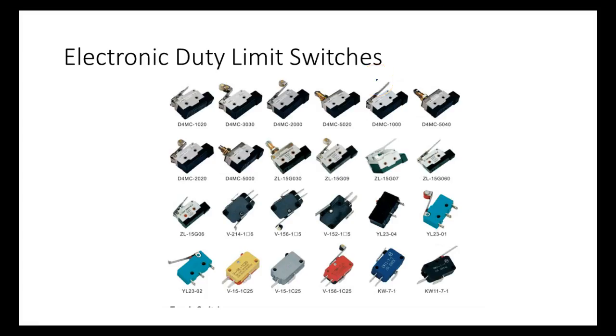Means small, yeah. So usually what we do is if my limit switch is going to run a load, then we're going to use a pilot duty or a heavy duty limit switch. If my limit switch is going to input into a PLC, we probably use one of these little guys, because they're not running a load, they're just putting either a true or a false into my PLC. So we don't have to have big relays, big limit switches for that.